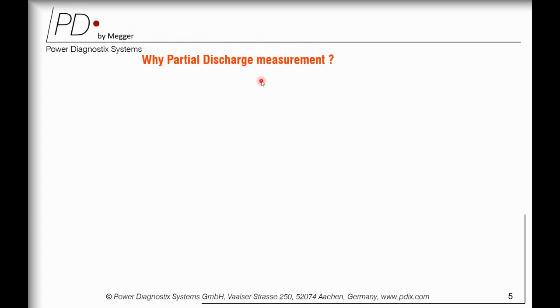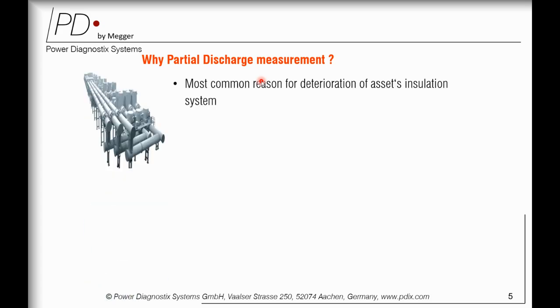So the first question is always why we need to do PD, because we are already doing various testing on our asset. When we talk about GIS, we already have gas, and we always measure the pressure and leakage. And we all know that we prefer GIS because no maintenance is required.